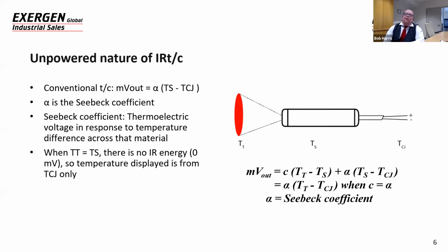The formula for a conventional thermocouple is a constant called the Seebeck coefficient times the temperature of the surface minus the temperature of the cold junction. A conventional thermocouple actually measures the temperature of itself, while a non-contact or infrared thermocouple measures the temperature of the target rather than the temperature of itself. The Seebeck coefficient is the electric voltage in response to a temperature difference across that material. So when the target temperature is equal to the sensor temperature, there will be no IR energy. When the IRTC looking at a target is at the same temperature, there's no IR energy coming from that.